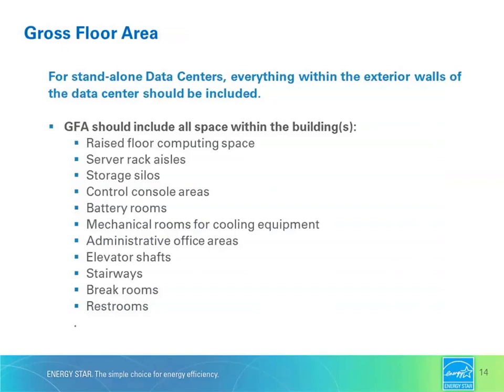Data center gross floor area for a standalone data center should include everything within the exterior walls of the building. So that includes all raised floor computing areas, of course, server rack aisles, storage silos, control console areas, battery rooms, mechanical rooms, administrative areas, elevator shafts, stairways, break rooms, restrooms, everything in the building.